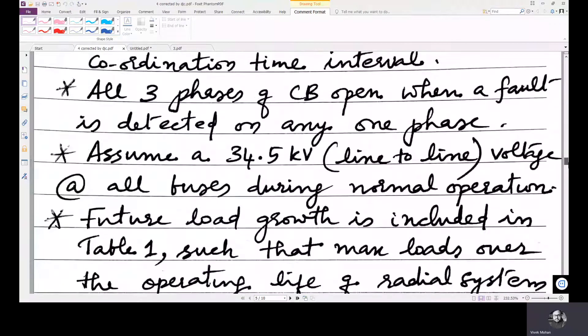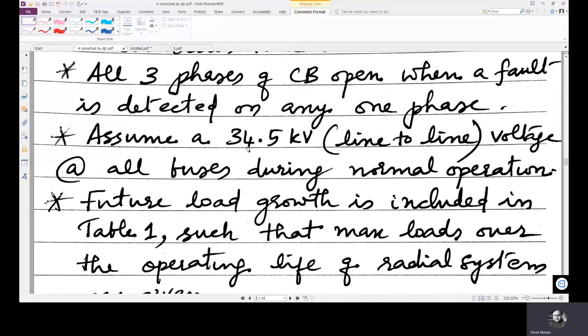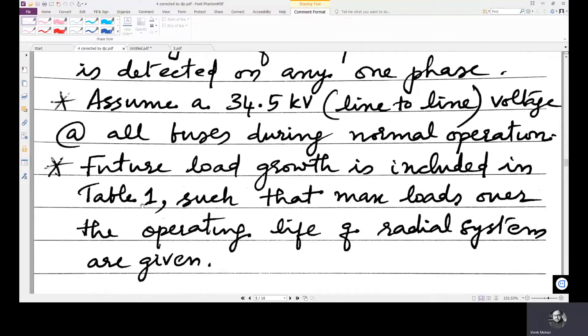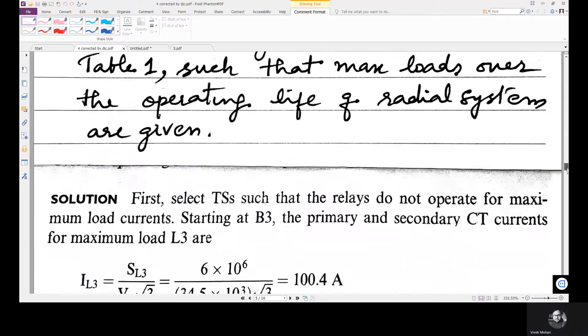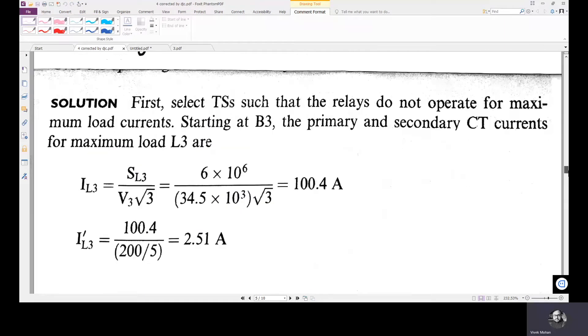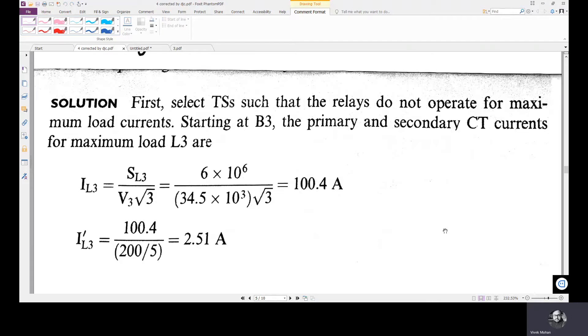In addition to the coordination time interval, the 34.5 kV line-to-line voltage is the power system voltage during normal operation, and future load growth is already included in the table 1 maximum loading values. Now we will go to the solution. First, we are selecting the tap settings such that relays do not operate for maximum load currents, since maximum load current is normal current and not fault current.